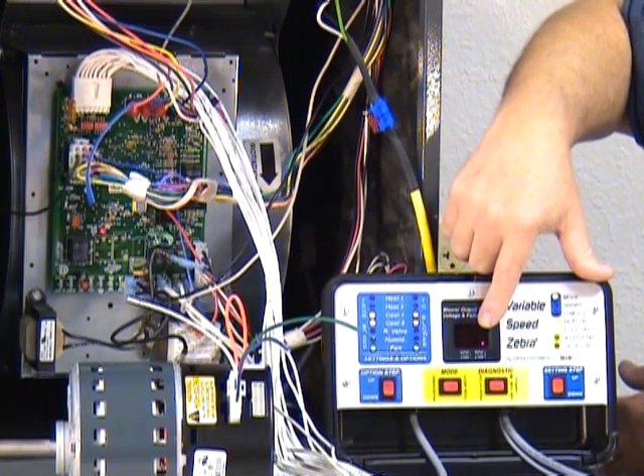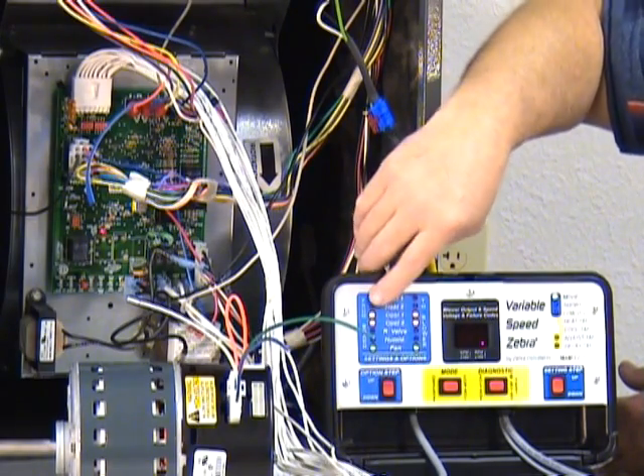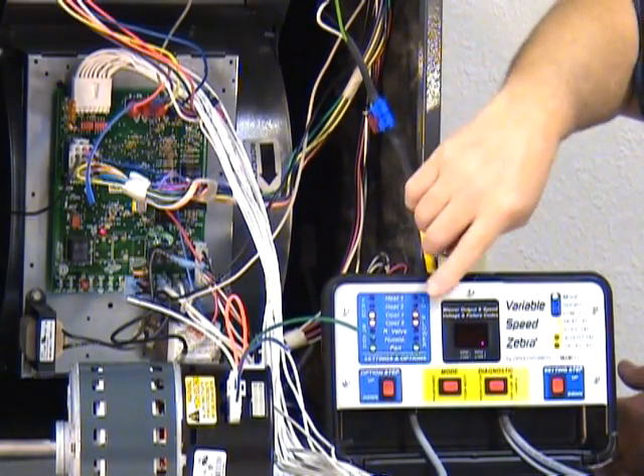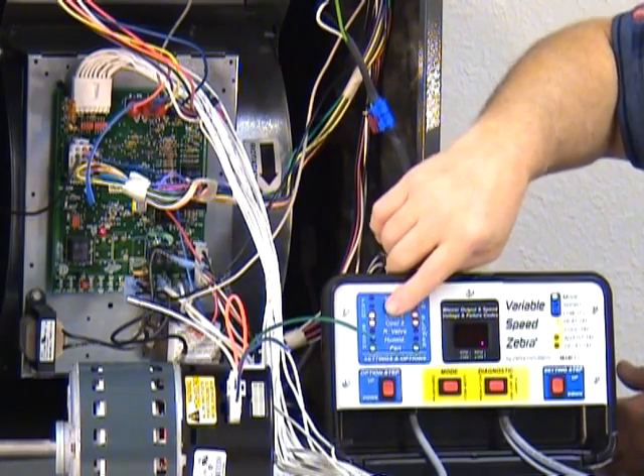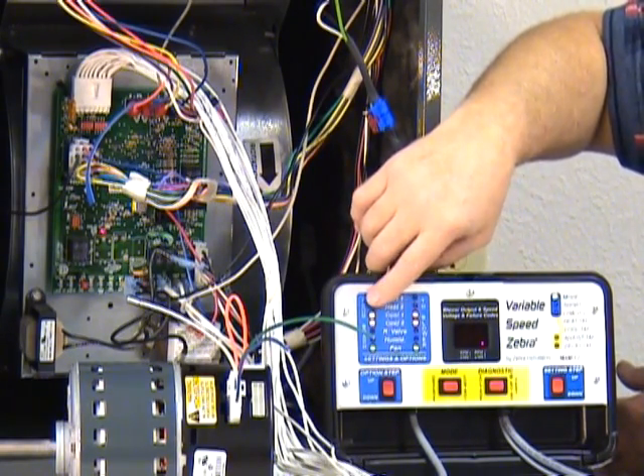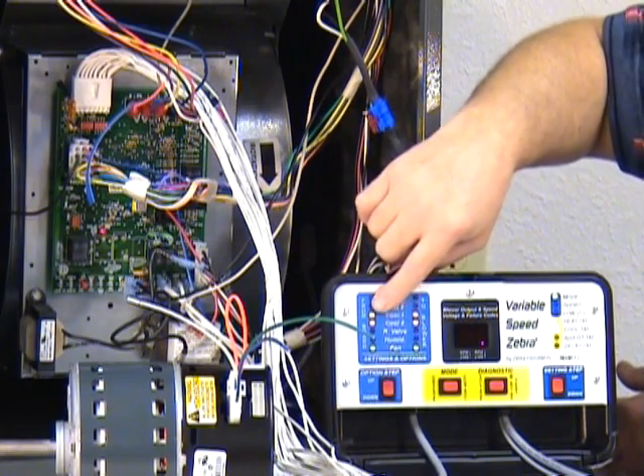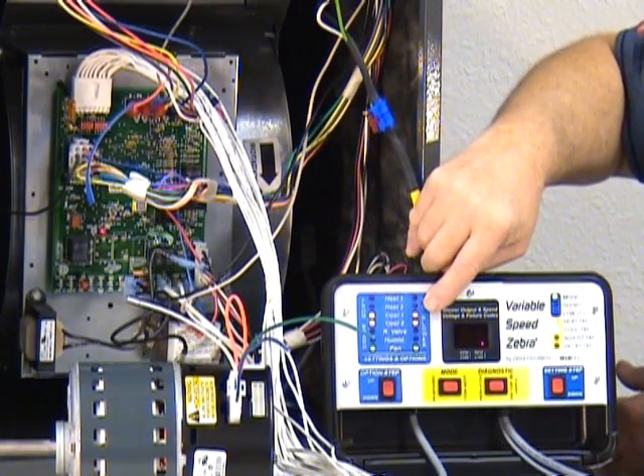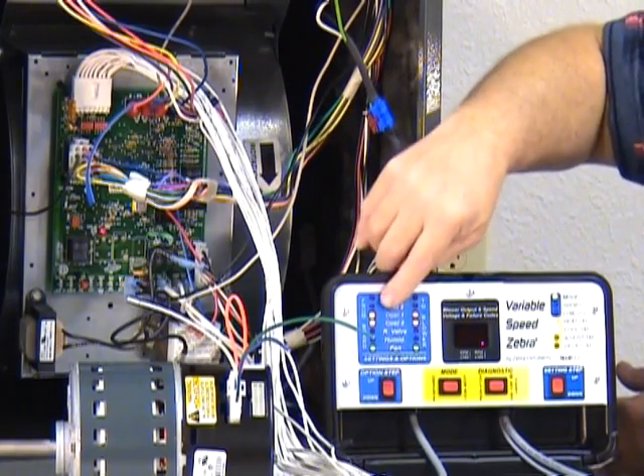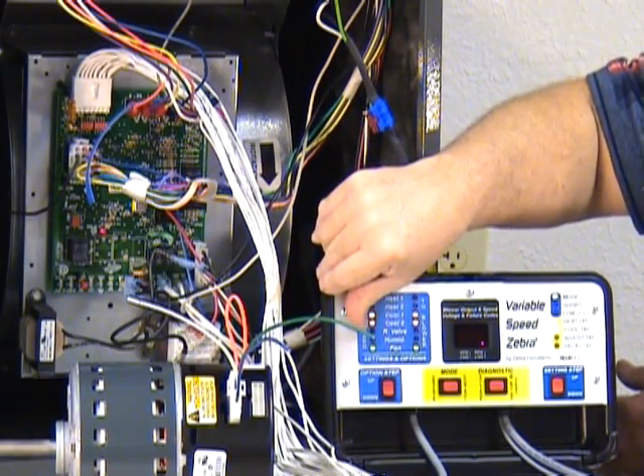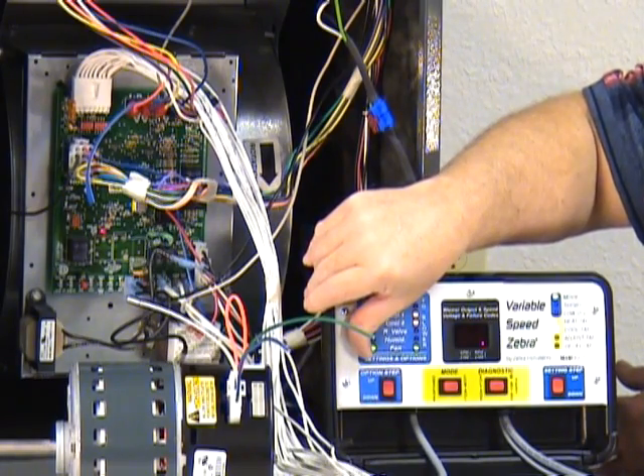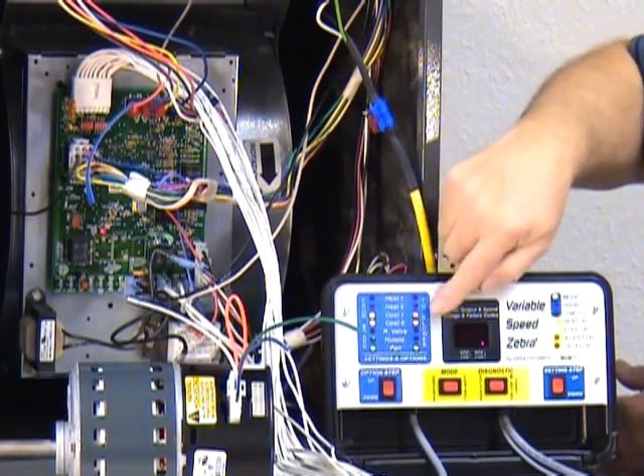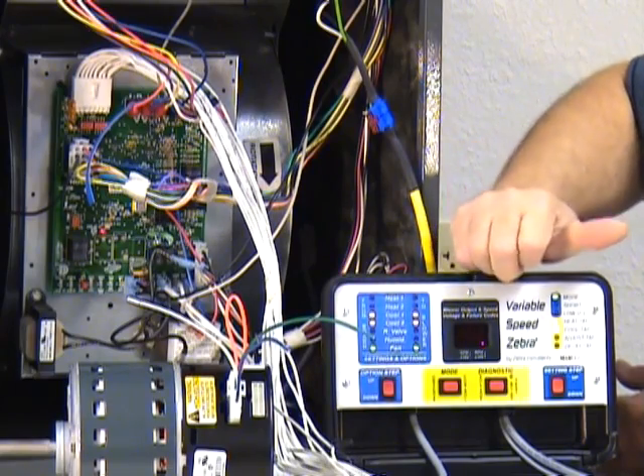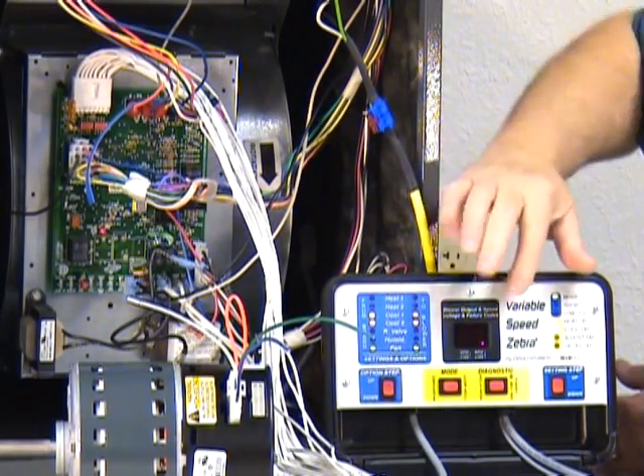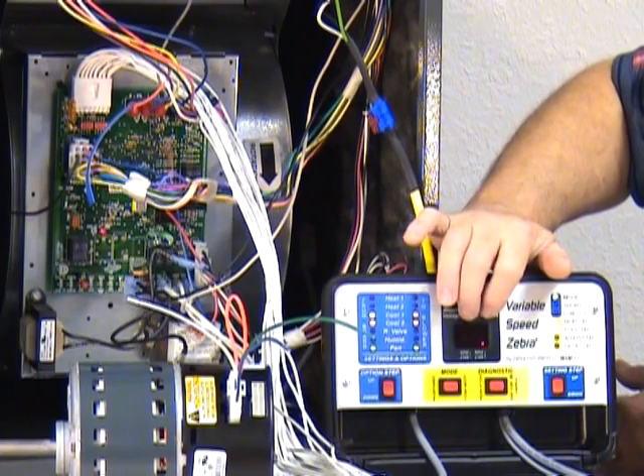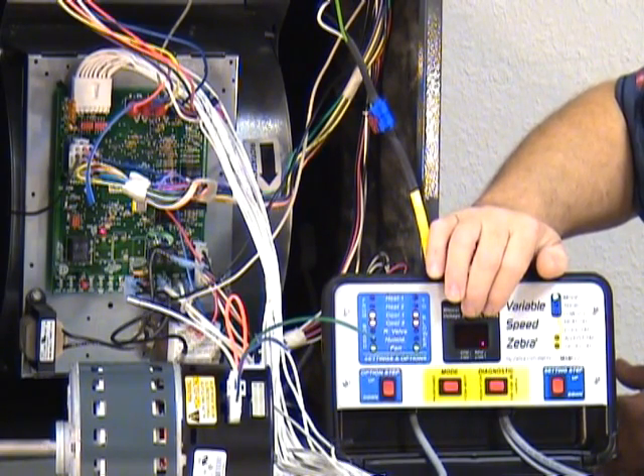But what I'd like to do is explain that, for instance, we put the thermostat, or the ZebraStat, a moment ago into high-speed cool mode. When you do that, if your system is a two-speed system, then both of these lights are going to come on also, indicating that it's receiving a low-speed cool and a high-speed cool, and of course the fan signal from your board. It's also passing those along to the motor. If the motor's power connector was plugged in right now, you'd be seeing a CFM and RPM significantly higher than what we saw a few moments ago.